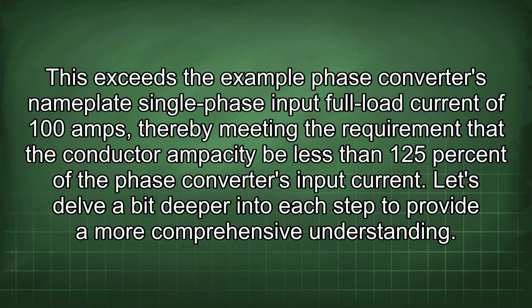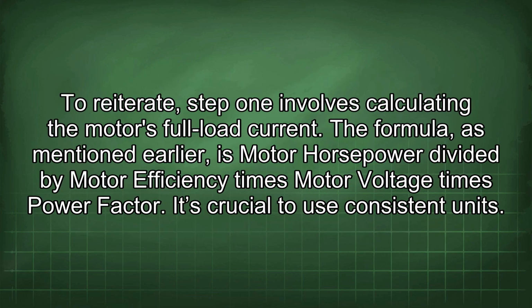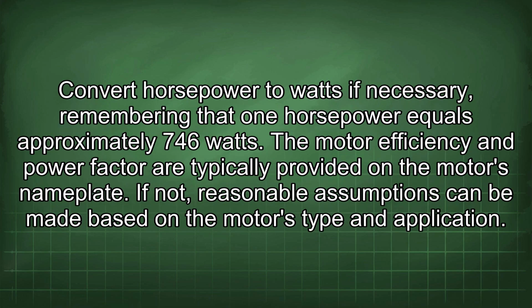Let's delve a bit deeper into each step to provide a more comprehensive understanding. To reiterate, step 1 involves calculating the motor's full load current. The formula, as mentioned earlier, is motor horsepower divided by motor efficiency times motor voltage times power factor. It's crucial to use consistent units. Convert horsepower to watts if necessary, remembering that 1 horsepower equals approximately 746 watts.